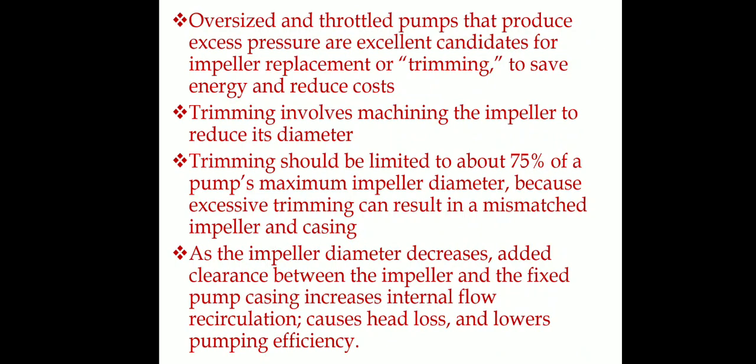The impeller is attached to a machine tool, which cuts off the outside diameter. The trim should be limited to about 75% of the pump's maximum impeller diameter. The impeller diameter trim must be carefully managed.